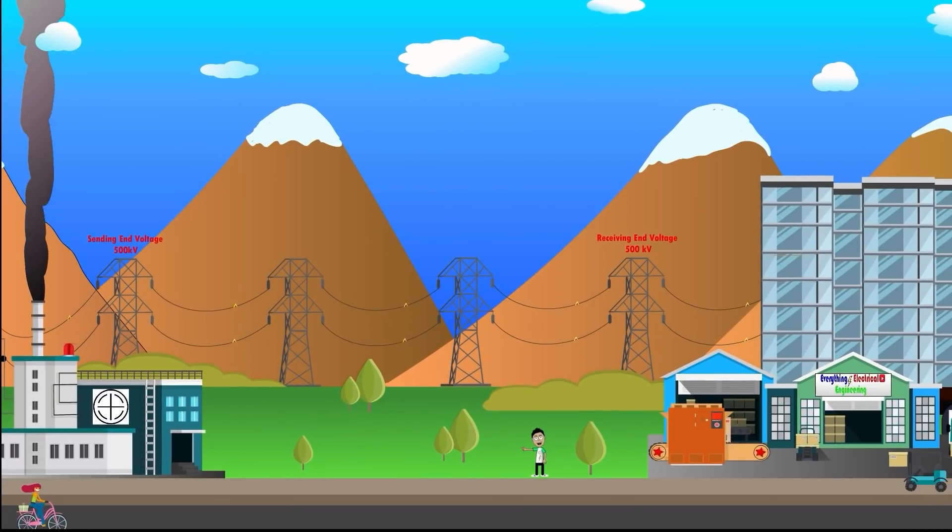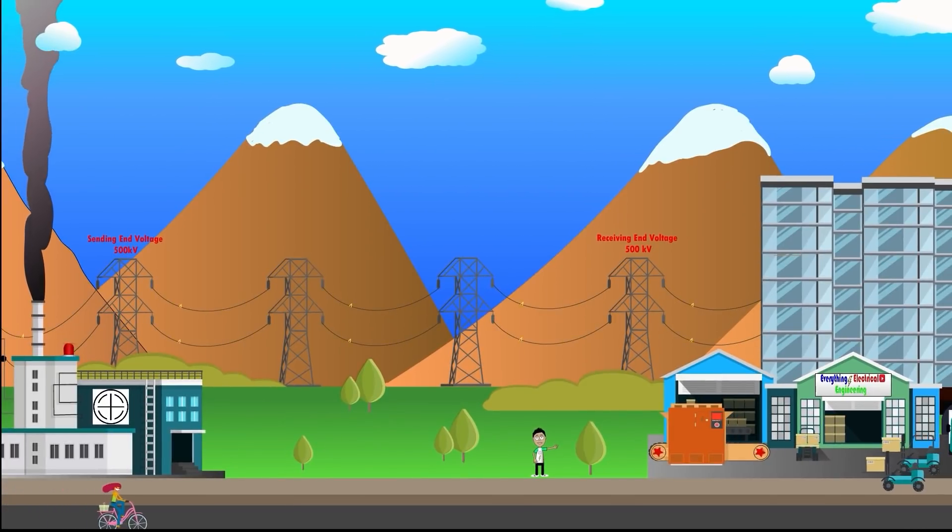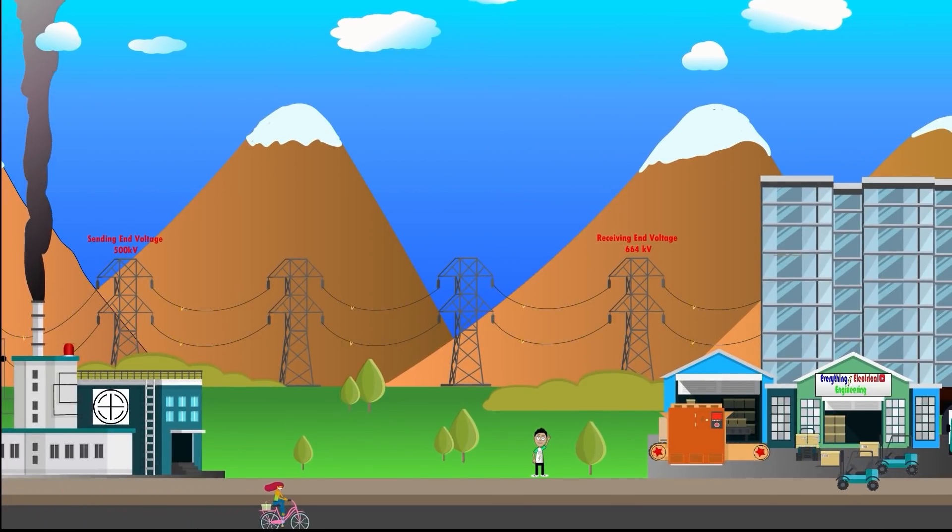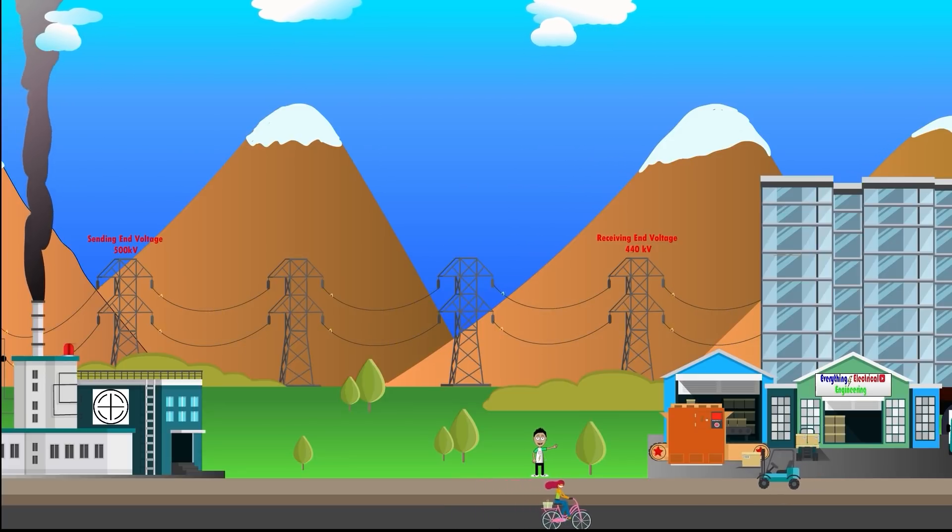Considering power being transported from generation to load center for medium to long transmission lines, if the line is lightly loaded or no load is applied the voltage at the receiving end will be larger than the sending end. This is known as the Ferranti effect. Conversely for heavily loaded lines the voltage at the receiving end will decrease due to the power factor of the loads applied.